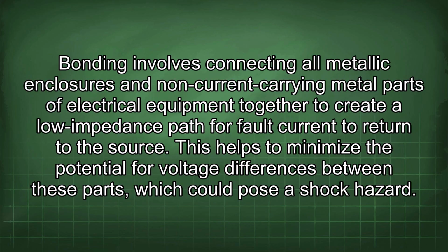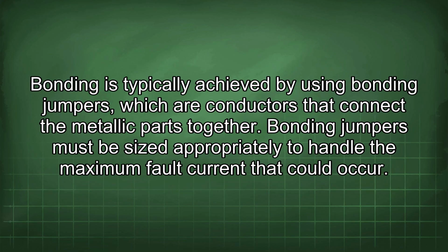Bonding involves connecting all metallic enclosures and non-current carrying metal parts of electrical equipment together to create a low impedance path for fault current to return to the source. This helps to minimize the potential for voltage differences between these parts, which could pose a shock hazard. Bonding is typically achieved by using bonding jumpers, which are conductors that connect the metallic parts together.